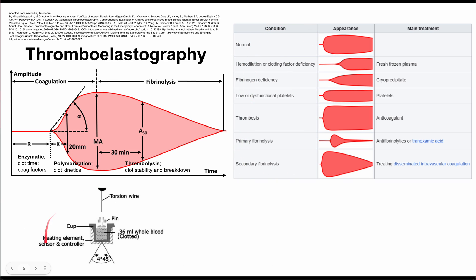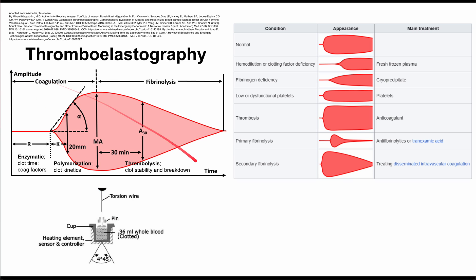Here's a small diagram that gives you a brief look at how it works. You put a small amount of whole blood into a cup, and this cup rotates. You insert a pin into the blood, and as the blood clots, the pin will begin to deviate. You then measure the amplitude of those physical deviations across time, and you produce a plot that looks like this.